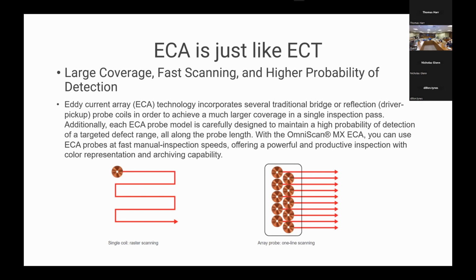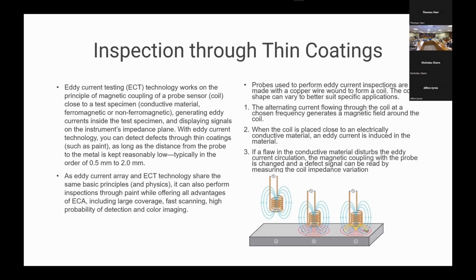With the OmniScan MX ECA, you can use ECA probes at a fast manual inspection speed, which offers powerful and productive inspection with color representation and archiving capability. You can also perform inspection through thin coatings. Typically in the order of 0.5 mm to 2.0 mm with eddy current, but we do have several probes that we offer that you can perform inspection through coatings as well.